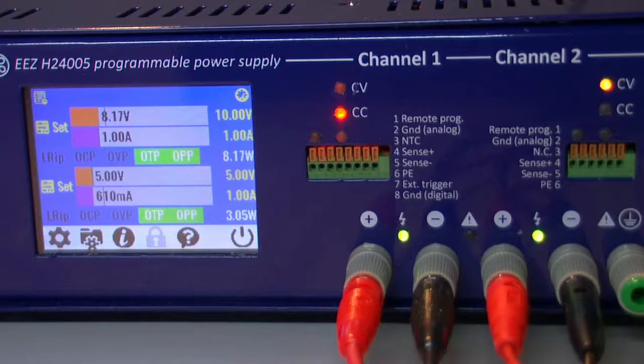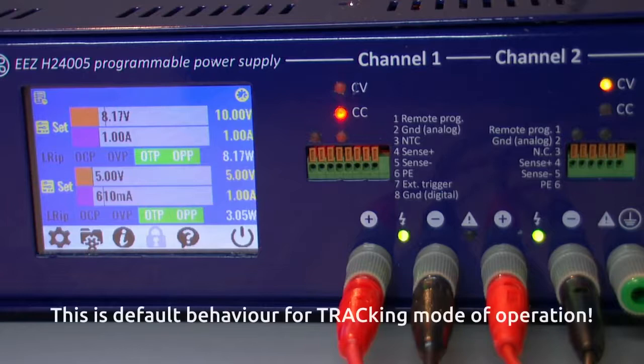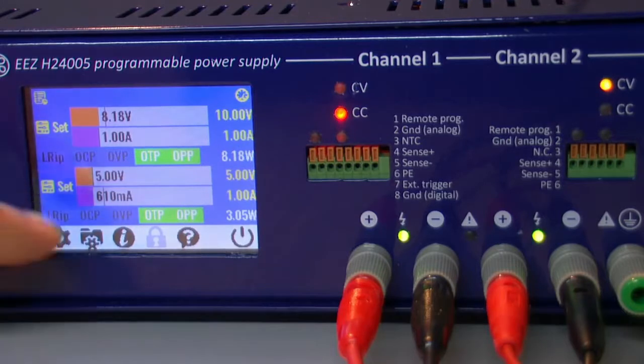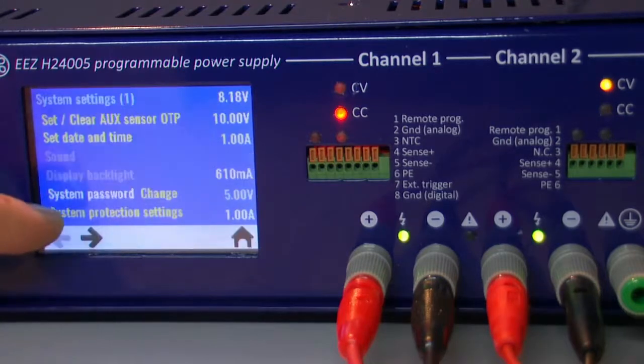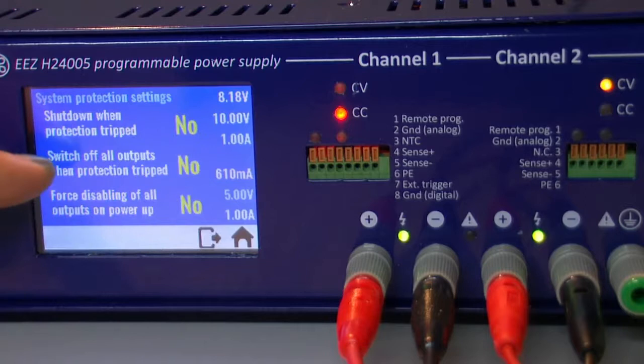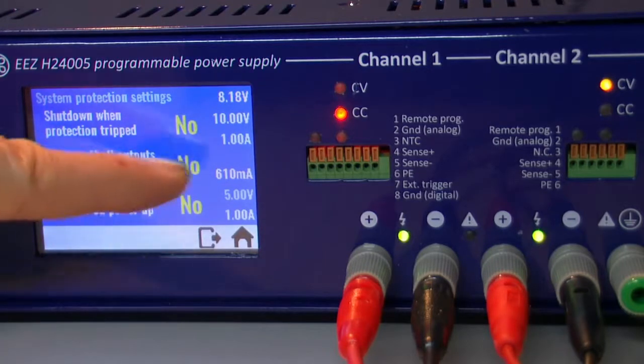Another possibility is also related to protection tripping. Instead of switching off the complete unit we can switch off both outputs if only protection tripped on one channel. Again we need to go to system settings and under system protection settings there is another option: switch off all outputs when protection tripped.